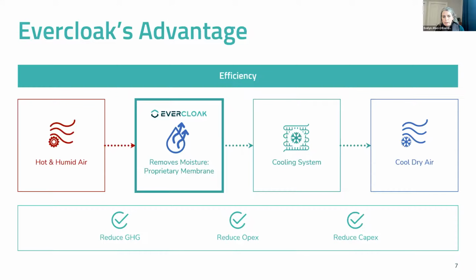At Evercloak, we separate that process. We're able to remove the humidity ahead of the cooling system and decouple it from the air temperature. This is our dehumidification technology: hot, humid air flows across our membrane, which is our enabling and core technology. The membrane is able to separate the water vapor very quickly from the air.